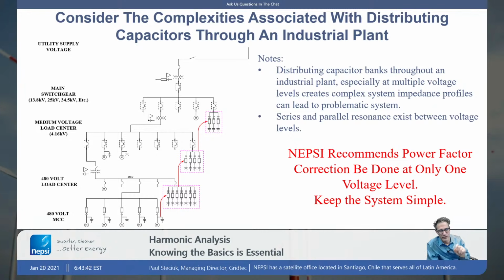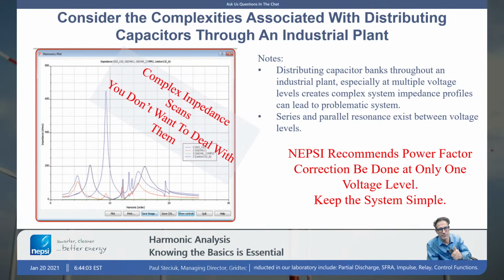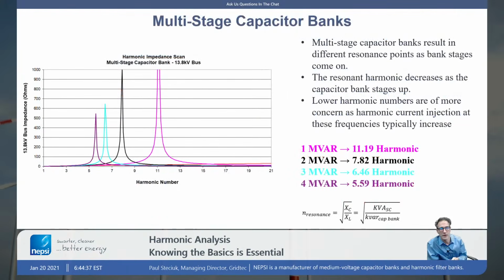The problem, though, is it makes the harmonic analysis very complicated. In a situation like this, I would have multiple parallel, multiple series circuits, and when we have multi-stage cap banks being used at each and every voltage level, it becomes very complicated. And so our recommendation is to only do reactive compensation, power factor correction, at one voltage level. It simplifies the system to just a small number of cases that you need to do simulation for. When you have a plant full of power factor correction capacitors at the low and medium voltage level, you get a much more complex impedance profile, and it changes throughout the day depending upon what capacitors are on, what loads are on. If you have a problem, you're going to have a very difficult time locating it and identifying it. So our recommendation is reactive compensation at one voltage level.